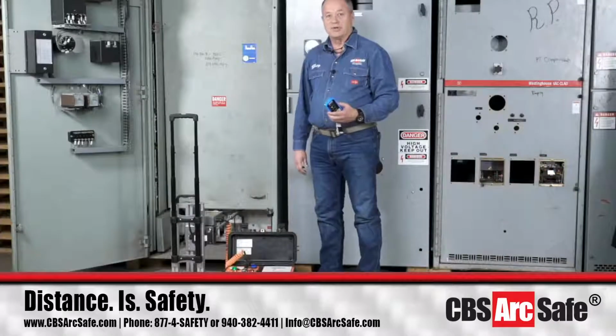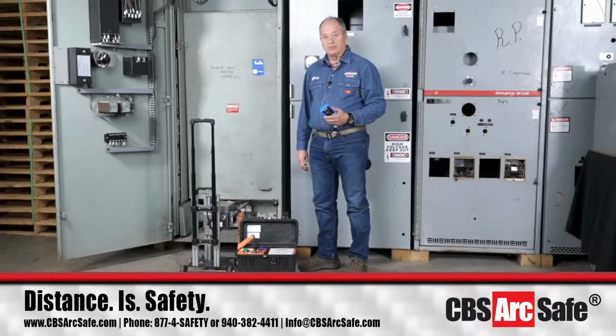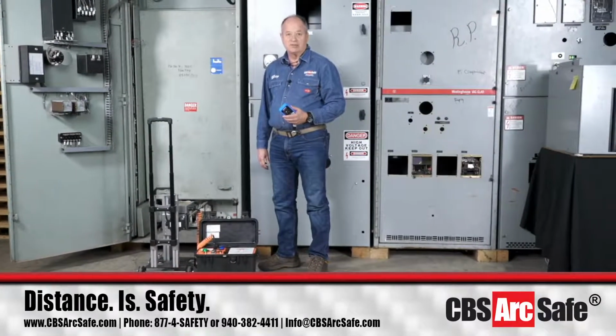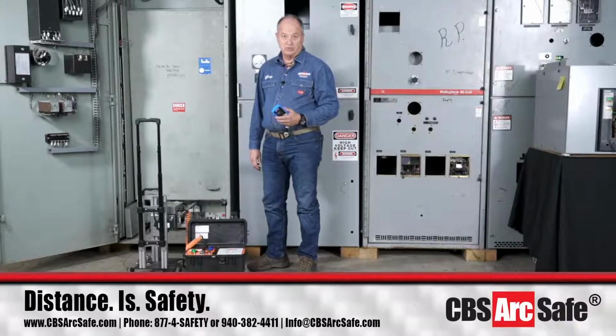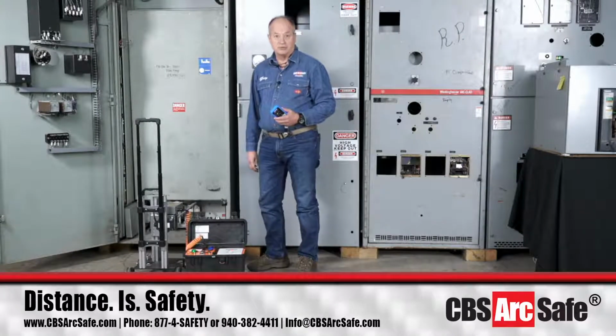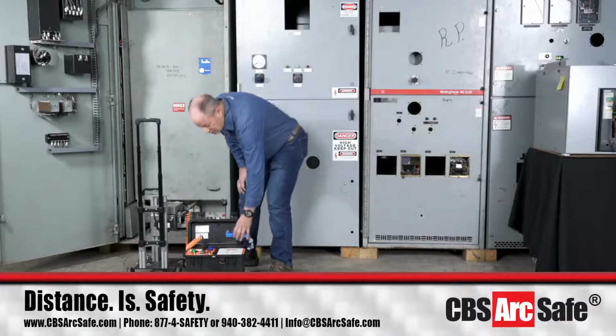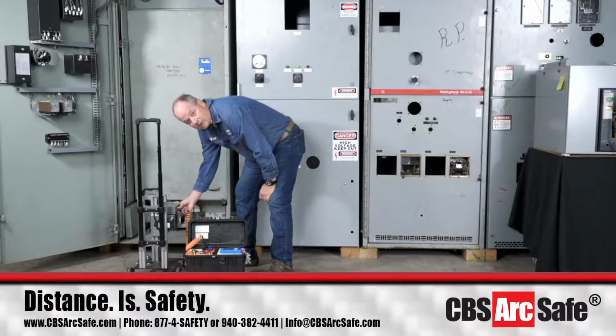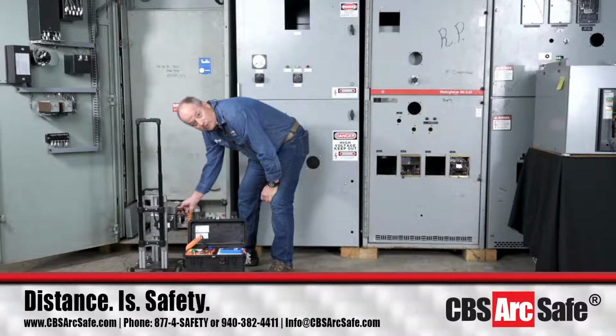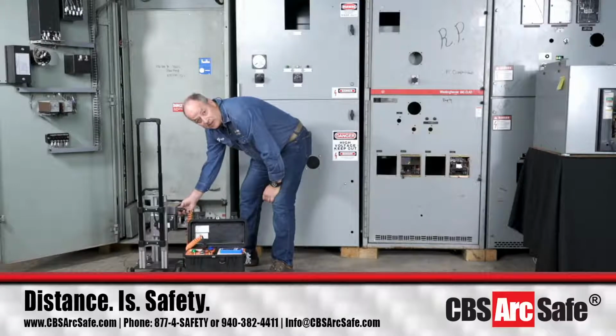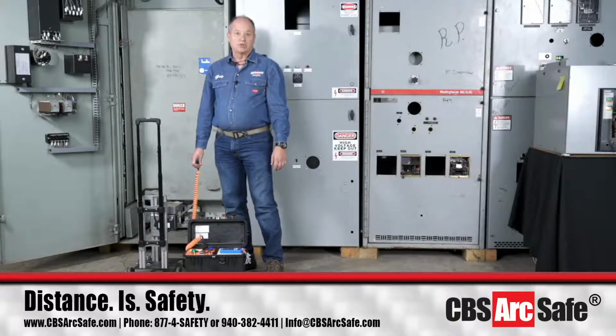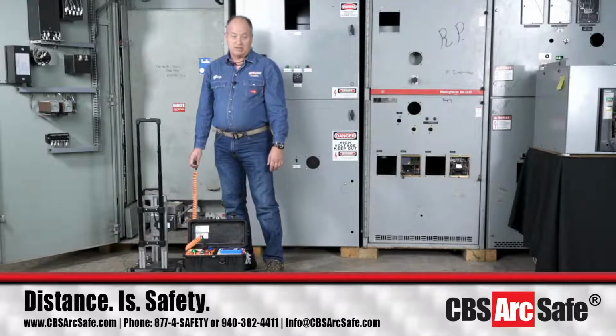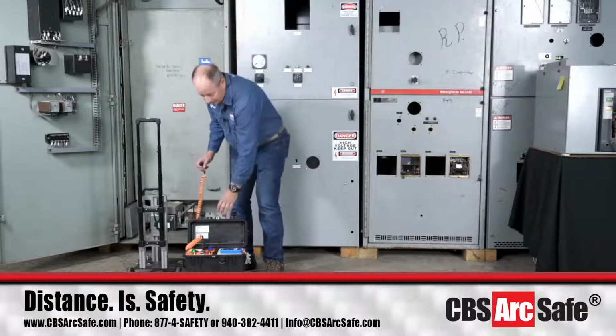And that's the completion of the operation. One of the first places I sold an RRS-1 to many years ago told me that because they started using remote racking, they weren't breaking the shutters in the DHP cubicles anymore from people trying to rack through the shutters. So the torque limits we set up on this are to help protect both you and the switchgear—we don't want to damage anything. More torque is not the answer. If the system shuts off because it runs into a torque issue, remember, it's trying to tell you the cubicle needs maintenance, and you need to address that.